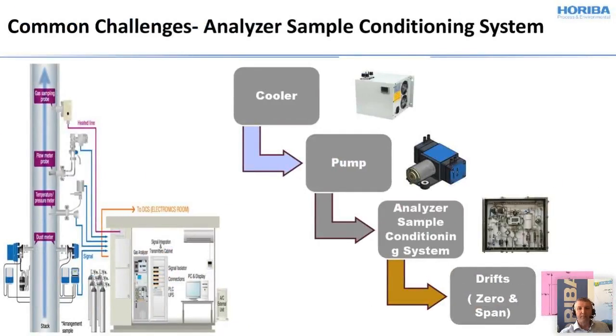So the next one is the sample handling system located in the analysis cabinet, which might be located in an air-conditioned shelter or outside, depending on the customer's request. Talking about cooler, pumps, analyzer, sample conditioning system, the final one, and talking about some drift, which also needs to be considered for the analyzer. The cooler is mostly of thermoelectric type. This causes problems in due course of time with leakage of refrigerant gases.